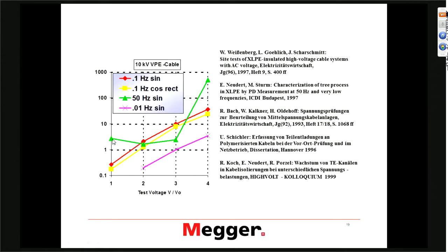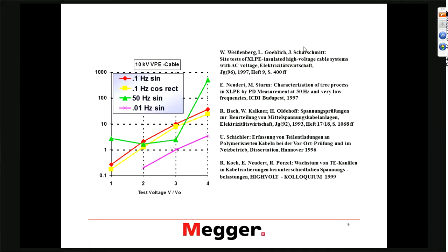At 60 Hz, the behavior is very almost linear from operating voltage to two times to three times operating voltage, but then it takes off very quickly. That's the reason why when you do power frequency testing, you don't want to come close to that point, because it can really create a domino effect in your cable. That's also why when we do PD testing at power frequency, we normally don't want to exceed the 2 per unit level — otherwise you can get in a runaway situation.